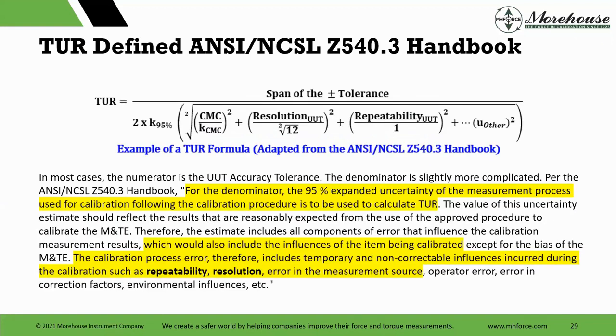So what's really important here is this definition for the denominator that I have highlighted, because for the denominator, the 95% expanded uncertainty of the measurement process used for calibration is used. And we've simplified this formula from what's below, which basically says influence of the item being calibrated, except for the bias of the M&TE, the calibration process error therefore includes temporary and non-correctable influence incurred during the calibration, such as repeatability, resolution, and error in the measurement source, operator error, error in correction factors, and environmental influences. All these are very important.